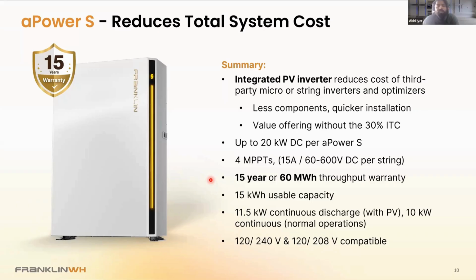Worked with a few installers where there are some restrictions coming from ESAs with regards to how much kW your entire unit can actually put out, especially in the case of multiple batteries. So we have those capabilities. But again, the thing to keep in mind is 10 kW continuous is what is going to be on the aPower S data sheet. We do have mention of 11.5, but that's only when there is PV available.